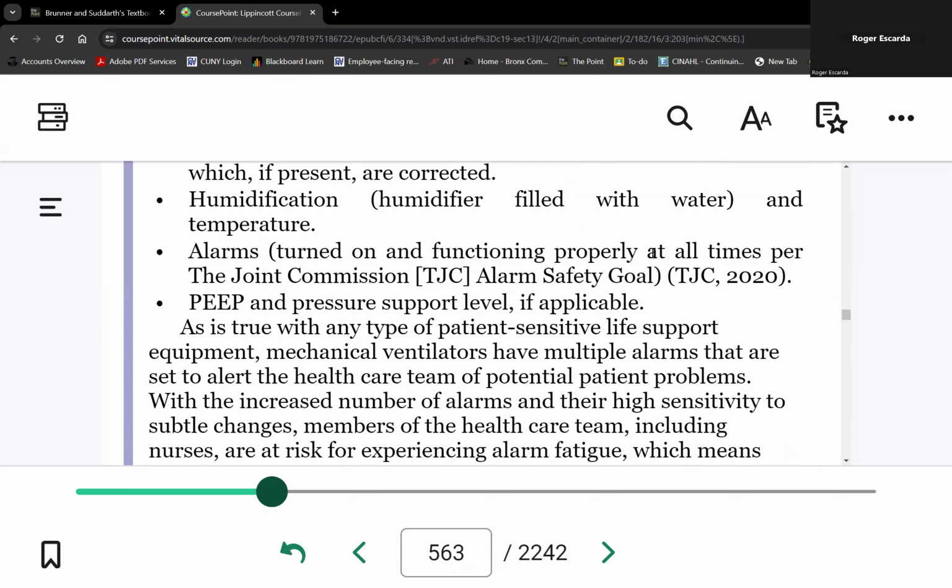Okay, alarms. For our purpose, we'll only talk about two alarms, either high pressure or low pressure alarm. I repeat, there's a resistance between the vent and the lungs, because the lung doesn't have a hole. So think of the lungs as a plastic bag or a balloon, right? And then the vent will push air into that balloon. Is there an unlimited amount of air that it can push into that balloon of your lung? No, of course. There's a limitation, right?